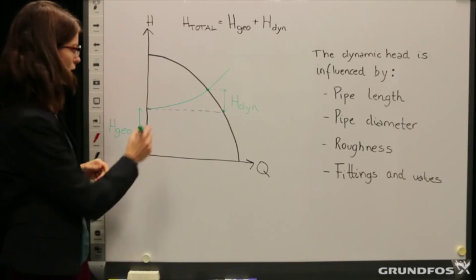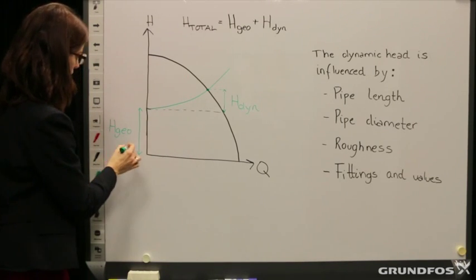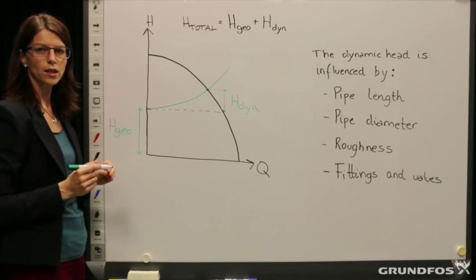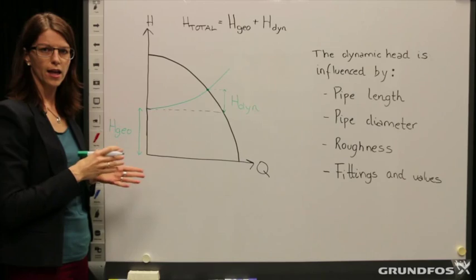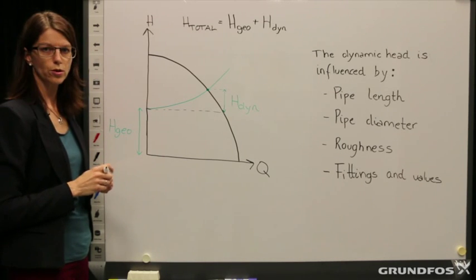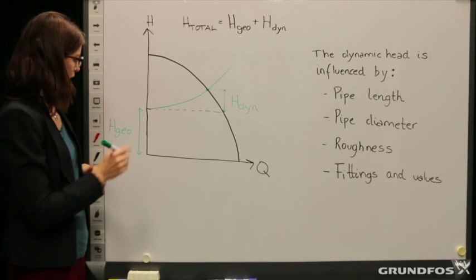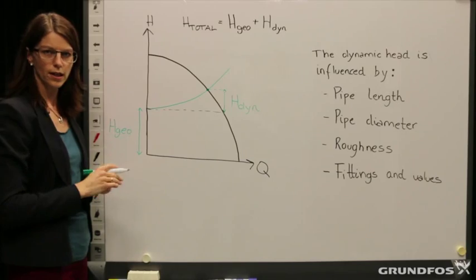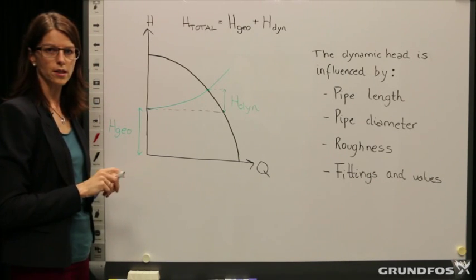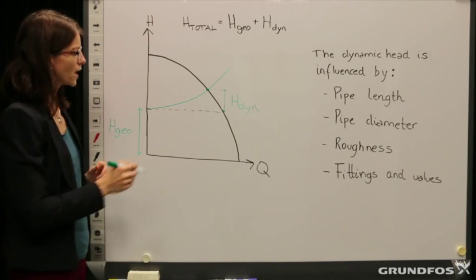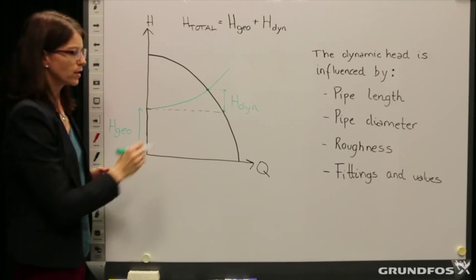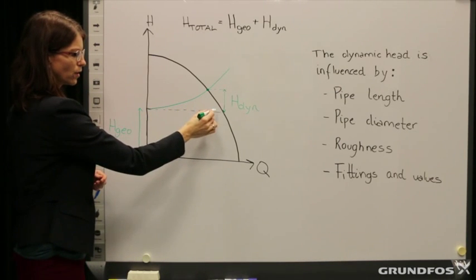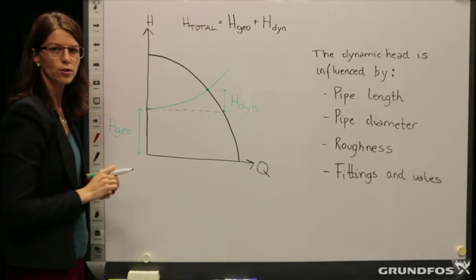I have drawn a curve here with a system curve and a pump curve. The geodetic head is characterized by the height between the pump and the sewage mains where the wastewater is transported to. We say that it is a constant — it can vary a little bit depending on the level in the lifting station or pumping station. The slope of the system curve is the dynamic head, and that is a very varied value depending on the flow.